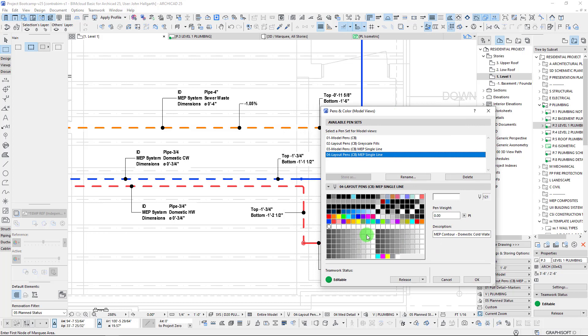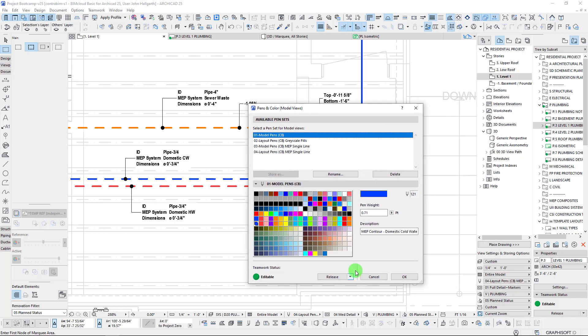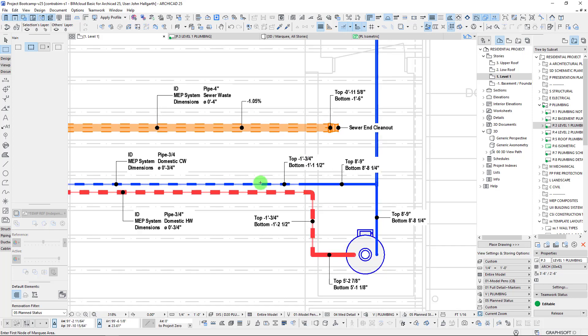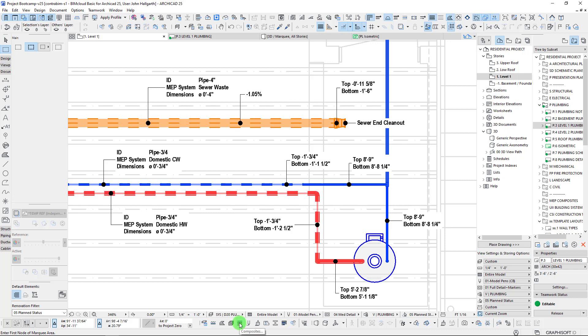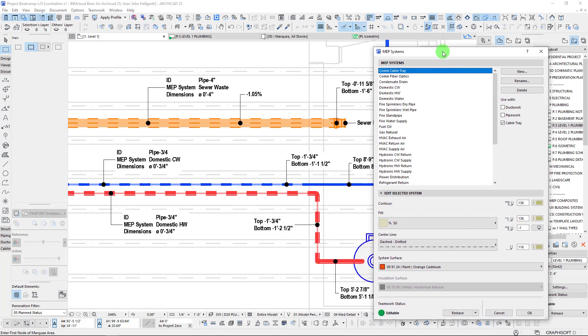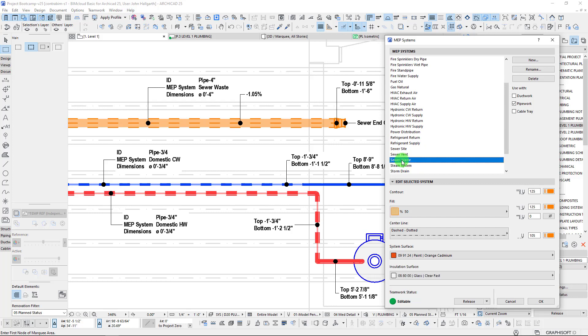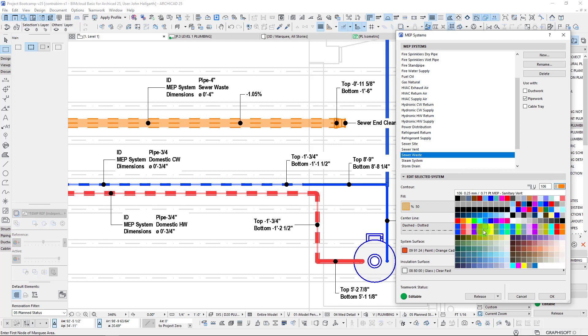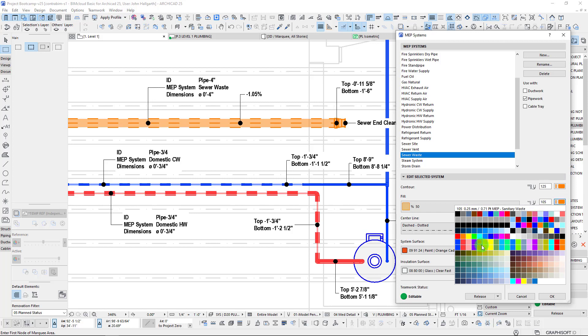So we can either darken our contours and fill pens, or switch those over to white — with grayscale for everything else. That's how we're achieving this. It's pretty straightforward and easy to use. It does take up a chunk of our pens, but we still have plenty for a range of colors and specific purposes, so it's not really an issue. Let's take a closer look by jumping into our MEP attributes. In our MEP preferences, let's go to the sanitary waste system to show where these pens are getting mapped. Our contour pen here is mapped to that second row, which goes white.